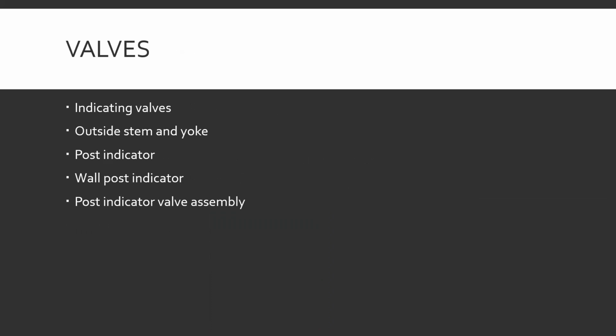Valves. All these coming up are indicating valves. What do they indicate? They indicate whether they're open or closed. So you can look at them and go, oh, that valve is open, there's water going through it, or that one's closed, there's no water past it. There's outside stem and yokes, there's post indicators, there's wall post indicators, and our post indicator valve assembly. A lot of these kind of sound like they're related, and that's because, honestly, most of them are pretty much related. Context and design dictate what is getting used.